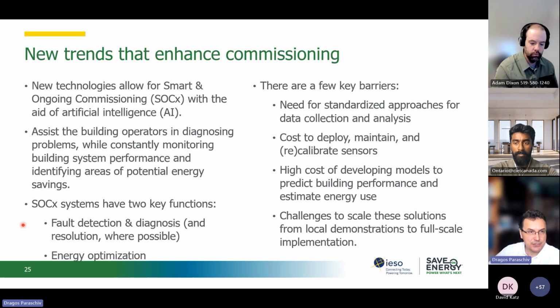So in operation, energy optimization — I mentioned complex chilled water plants that know when to push the cooling tower more or the chiller more, because they operate as a system. Some of these measures are implemented in our building system through the building automation system as a kind of continuous commissioning system.